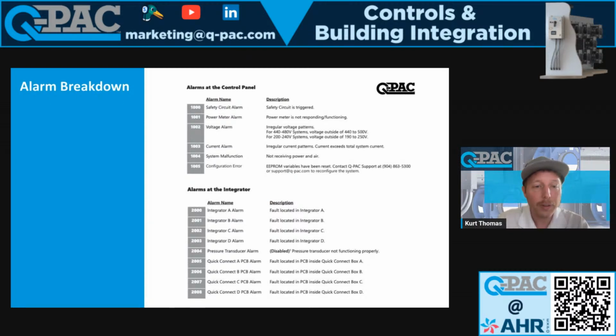Alarms at the integrator. So if you have an integrator A alarm, fault at integrator A, that just means that you may have an issue with the printed circuit board or some wiring inside of our control panel. It goes along with the quick connect box PCB alarm. You might see those in conjunction. Whenever that happens, it might mean that you just have a loose pin somewhere between the quick connect box and the fan. So really, to fix that, a lot of times you just need to follow the wires between the quick connect box and the fan itself.